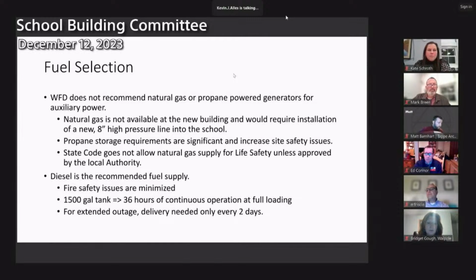Okay, this slide is dealing with the fuel selection. The Walpole Fire Department was approached regarding the fuel source. They did not recommend natural gas or propane power generators for the site. Natural gas was not available at the new building and would require installation of a new 8-inch high-pressure line to the school. Propane storage requirements were significant and increased site safety issues. And the state building code does not allow natural gas as a backup fuel source for generators that are providing life safety, which is your emergency lighting in the building, unless approved by the local authority, which goes back to the first bullet where the fire department did not recommend natural gas.